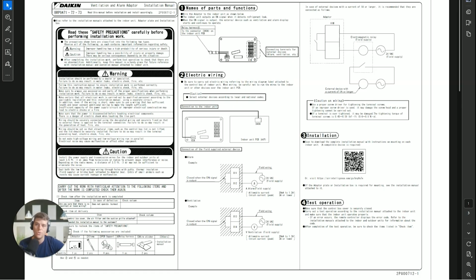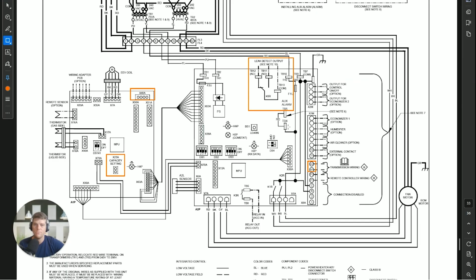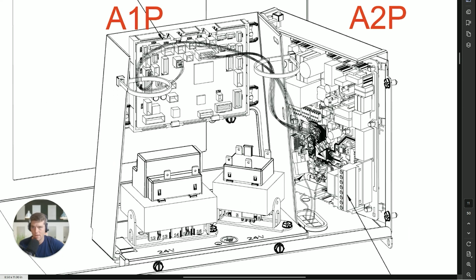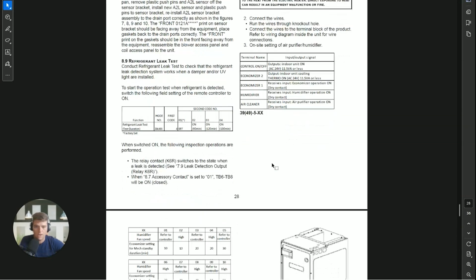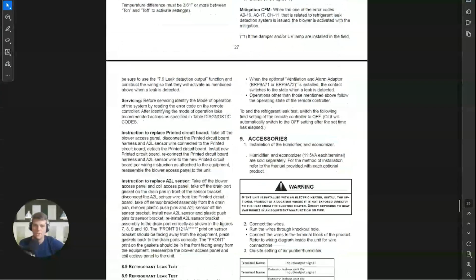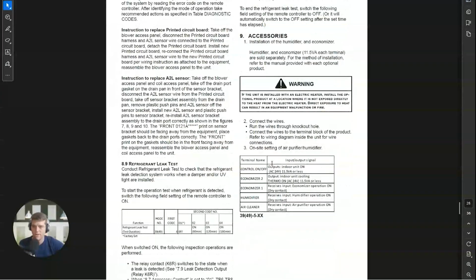If you're going to go back and use that relay that we showed here, the leak detection output, remember that these relays are rated for a small amount of actual current draw. So you don't want to just go in and, like the Daikin ones, we learned the hard way. Let's just put it that way. You can't run anything with a serious load through a Daikin accessory contact. It burns the thermostat out because the relay that's in it is not designed to handle that kind of load.